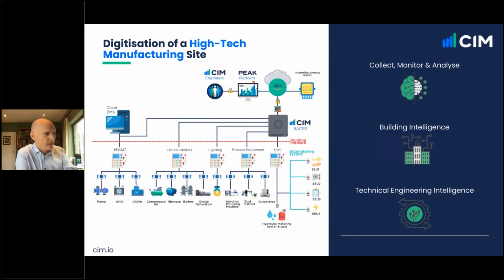Yeah, and again, this is a diagram showing the type of data sources that we can unlock, and it starts on the left-hand side. The HVAC is our primary value add to clients, and if you think of the large high-tech manufacturing sites, a big portion of their energy consumption is on HVAC because they're trying to maintain GMP or GxP conditions to manufacture product. That can often be quite expensive in terms of an annual energy bill, or a big portion of their energy bill, if things like free cooling are not an option because you can't bring in fresh air. Other plant and equipment that we're beginning to get data from is stuff like compressors.